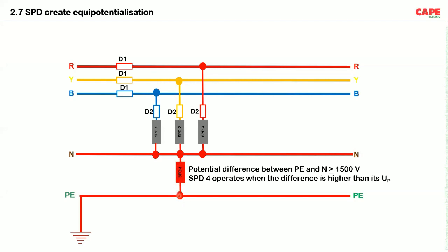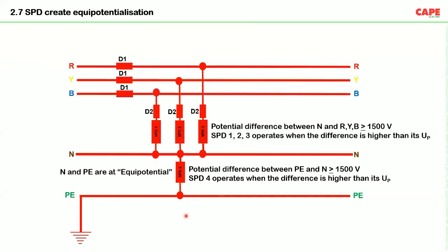As a result, what happens? Potential difference between PE and neutral for the time being has become 0. But the same high potential of the earth is now transferred to the neutral. Suddenly, between the neutral and the other phases, the same potential difference is applied. As a result, these 3 devices also will switch on and connect neutral and the other phases. So now we have created a situation which is a perfect equipotential bonding.